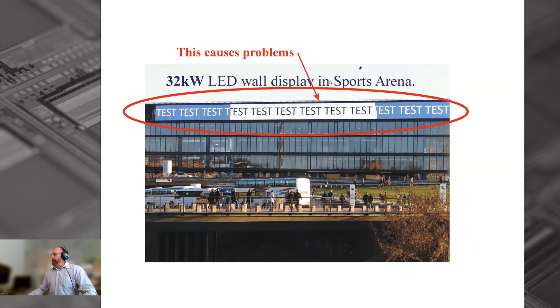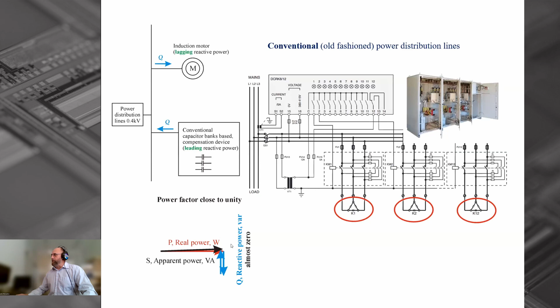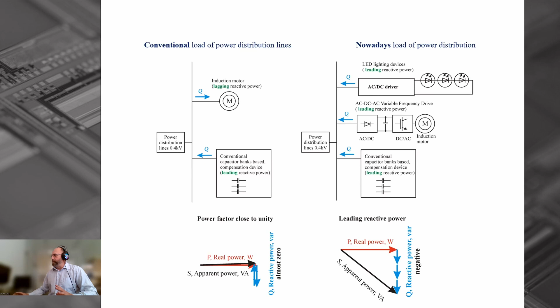nowadays power distribution lines. In conventional power distribution lines, we have loads such as induction motors. They consume positive reactive power. For reactive power compensation, capacitor-based compensator devices that produce negative reactive power were usually used, pushing the reactive power of the power distribution lines close to zero, a very good power factor. Nowadays, we have a quite different situation. The power distribution lines are loaded by lighting devices that produce negative reactive power, variable frequency drives that produce negative reactive power, and we also have the compensators left from the old days, which produce negative reactive power as well. We get the sum of the negative reactive power, a very bad power factor, and a lot of reactive power in the power distribution lines.